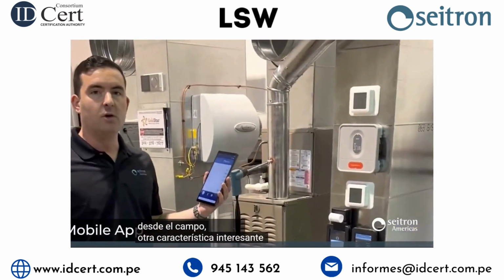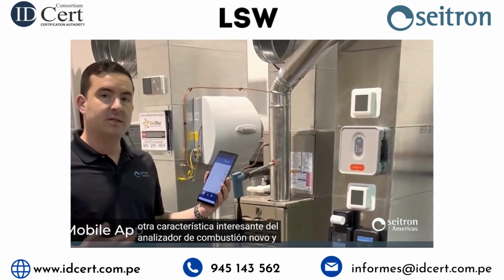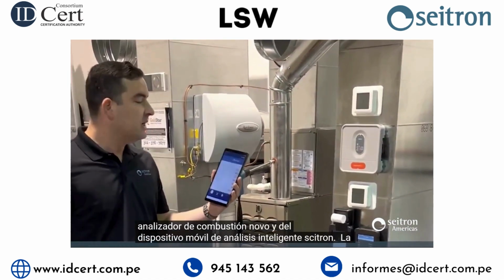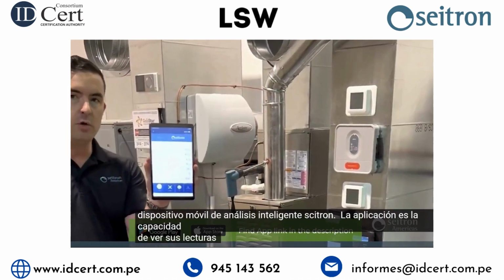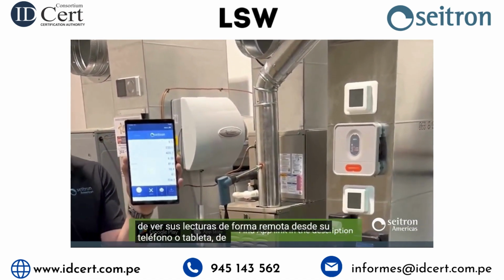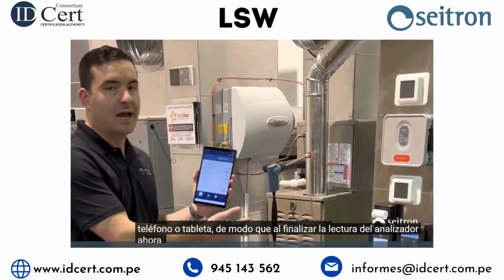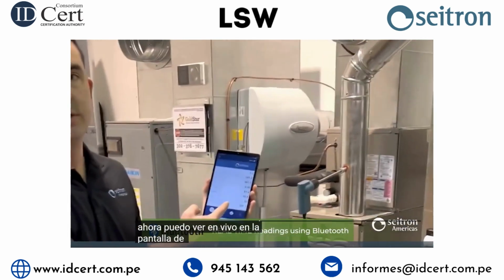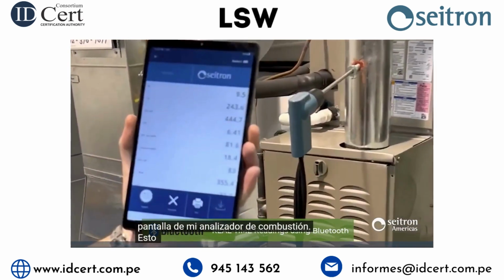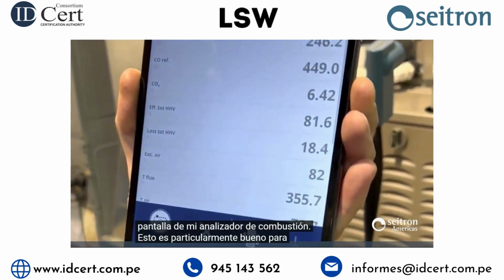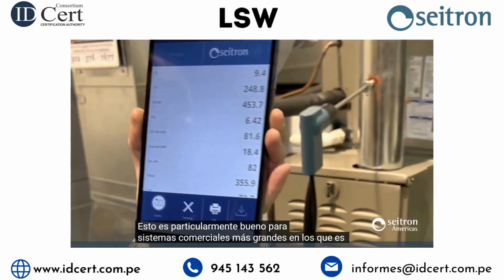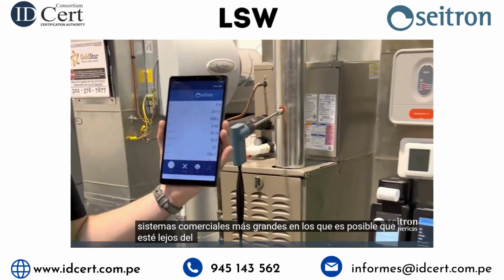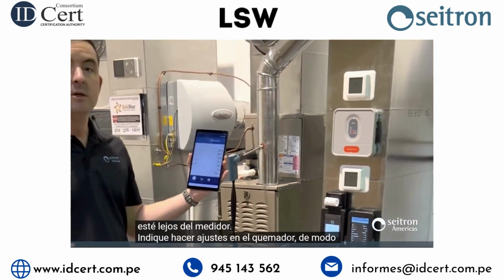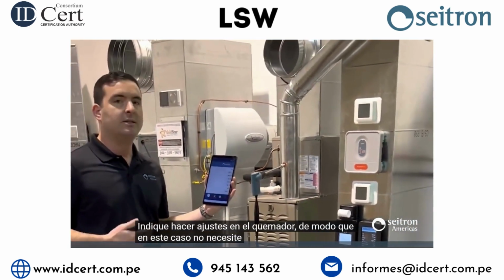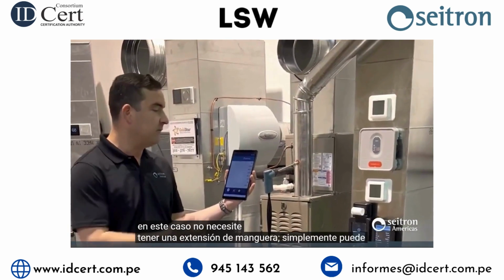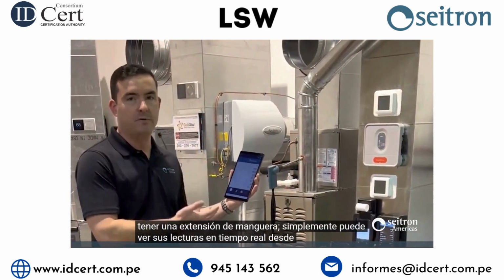Another nice feature of the Novo Combustion Analyzer and the SEITRON Smart Analysis mobile app is the ability to remotely view your readings from your phone or tablet. So anything the analyzer is reading, I can now see live on the display screen of my device. This is particularly nice for larger commercial systems where you might be standing far away from the measuring point making your burner adjustments. So in this case, you don't actually need to have a hose extension. You can simply view your readings in real time from your device, all right?